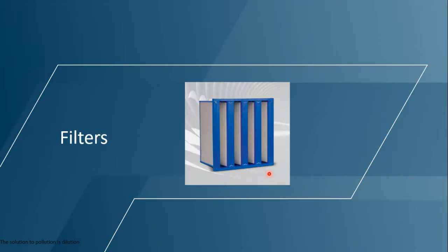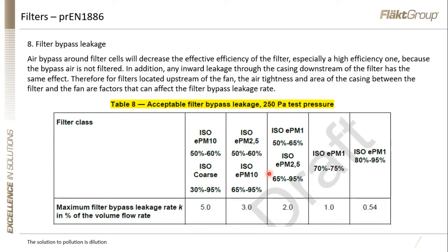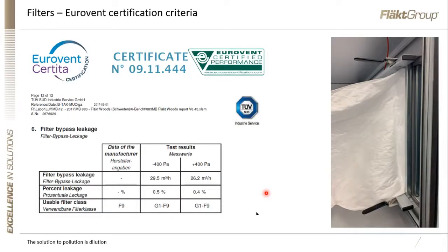And then filters, just following on from what Peter was saying earlier on, contained within the provisional EN 1886 is a section on acceptable filter bypass leakage. I'm not going to go into the details here because we don't have time, but these are the acceptable figures. And again, if you are Eurovent certified, Eurovent publish essentially the filter bypass leakage that's achieved when the unit is tested. And in this case, as you can see here, despite the fact the unit was tested with an F7 in old money filter, the bypass leakage was actually a classification F9. So in other words, there was virtually no bypassing of the filter frame through the air handling unit because of the nature of the way that we construct our filter frames.